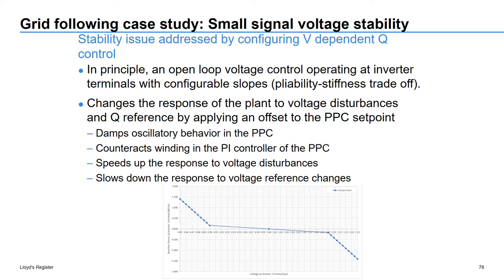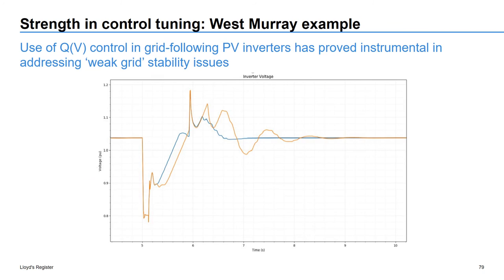By tuning this, we were able in the West Murray context to achieve damping of the oscillatory behaviour that was being observed. We were able to counteract wind-up of the PI controller, and we were able to speed up the response to voltage disturbances, which gives us an improvement in performance, as seen on the next slide. As this diagram shows, we were able, by tuning that Q of V control mode, to achieve substantial damping in what was a quite oscillatory response.